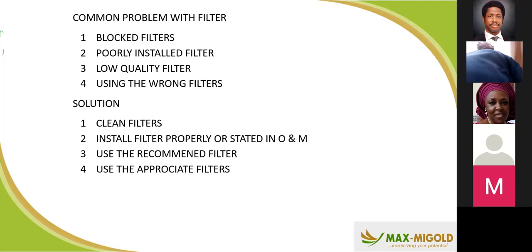Poor install filter can also affect it. If the filter does not cover the whole stretch where it's supposed to be, some dirt can enter the evaporator, and if dirt enters the evaporator, it will not work well. What is supposed to produce cold water, the cool air inside the filter, is retained because of that blockage, so you start seeing ice forming on top of it because there's no proper heat exchange.